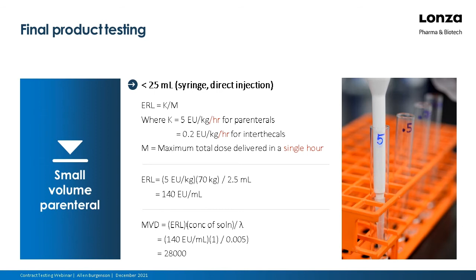For your maximum valid dilution, it's the endotoxin release limit multiplied by the concentration of the solution, which is usually 1, divided by lambda, or the sensitivity of your assay. Now, in the case of chromogenic and turbidimetric assays, it could be anywhere from 0.01 to 0.001, or for our chromogenic assay, it is 0.005. So the maximum valid dilution in this instance is 140 divided by 0.005 for our chromogenic assay to give you 1 to 28,000. So you can have a very good dilution scheme to overcome any problems that you may find.